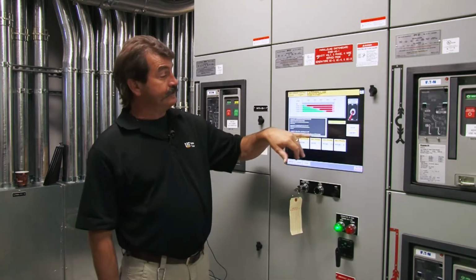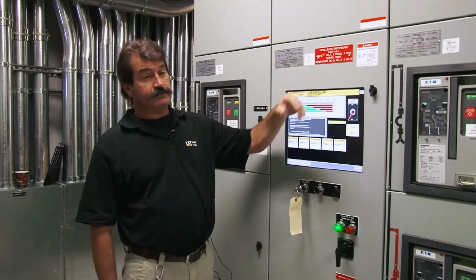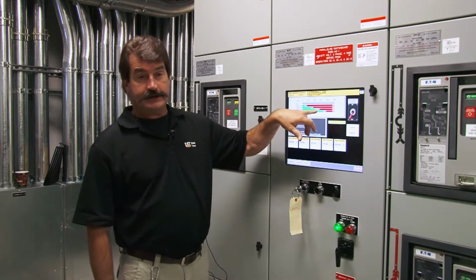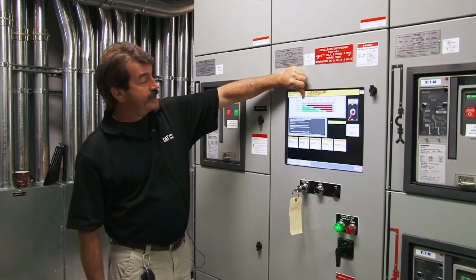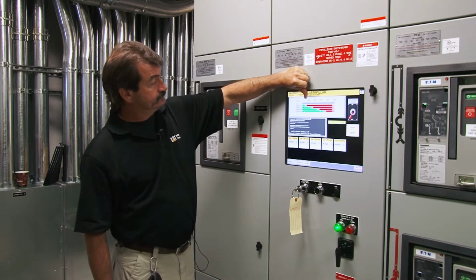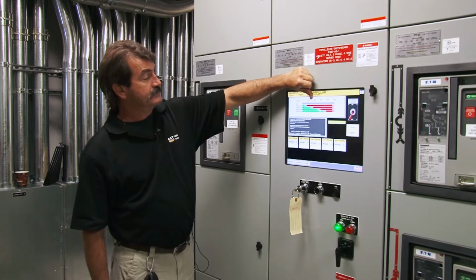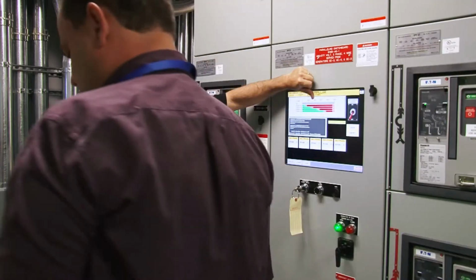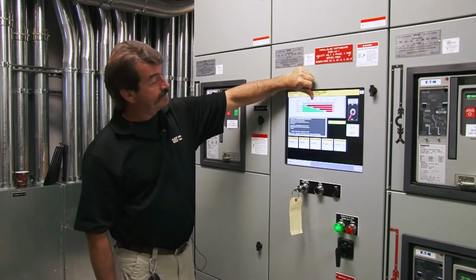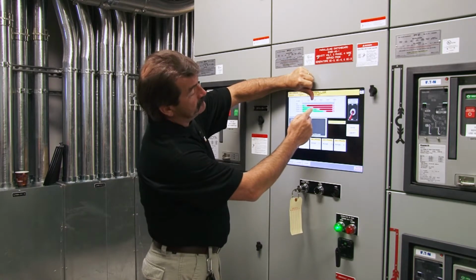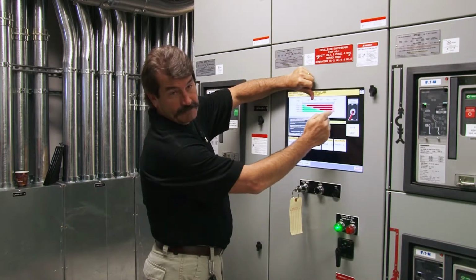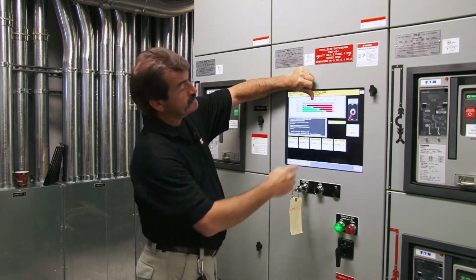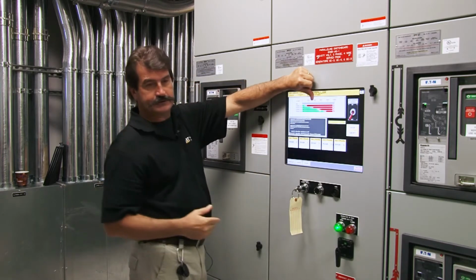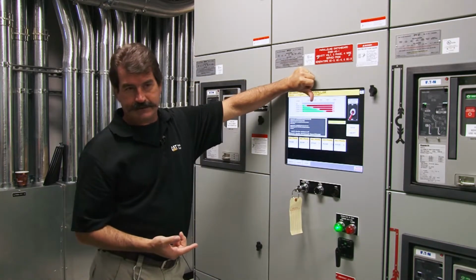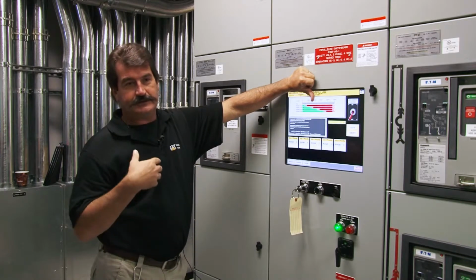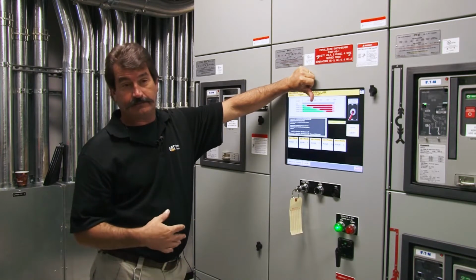And what would happen here is it would start shutting them down based upon this chart right here, depending on how much load you had. So if you're looking out here and you had, say, let's call it 4,000 kW of load that your generators had right there, anything in green that's above 4,000, it's going to shed those. So it would shed, of course, priority 5. Well, as soon as it shed your priority 5 gen, the first thing that happened is that any circuit breakers that are priority 5 would open, okay?